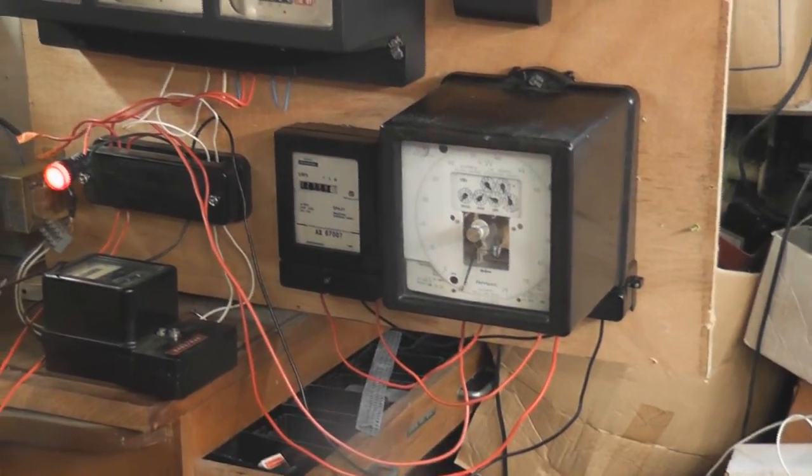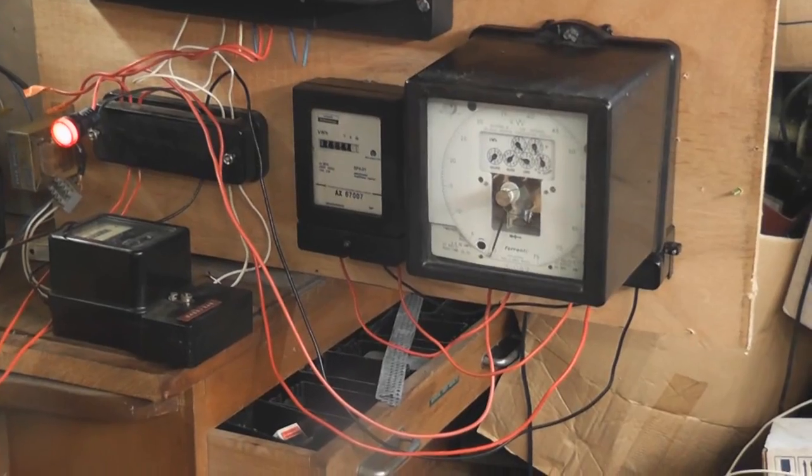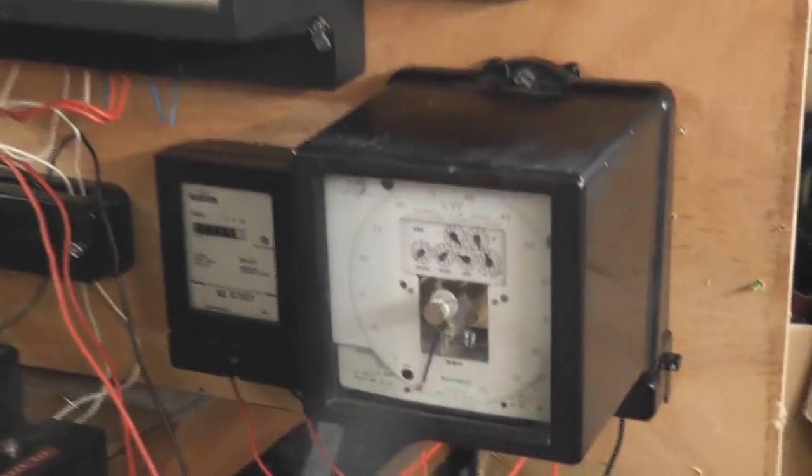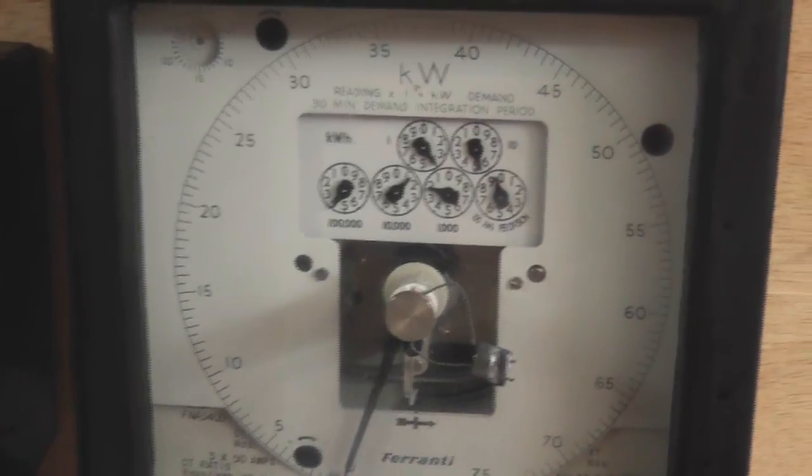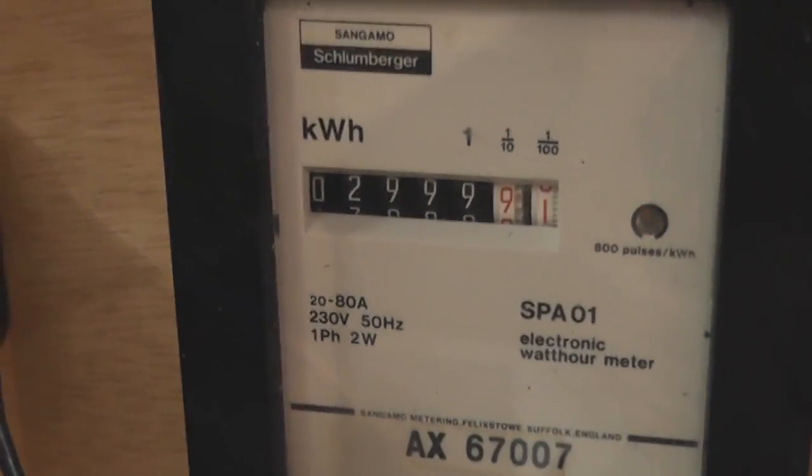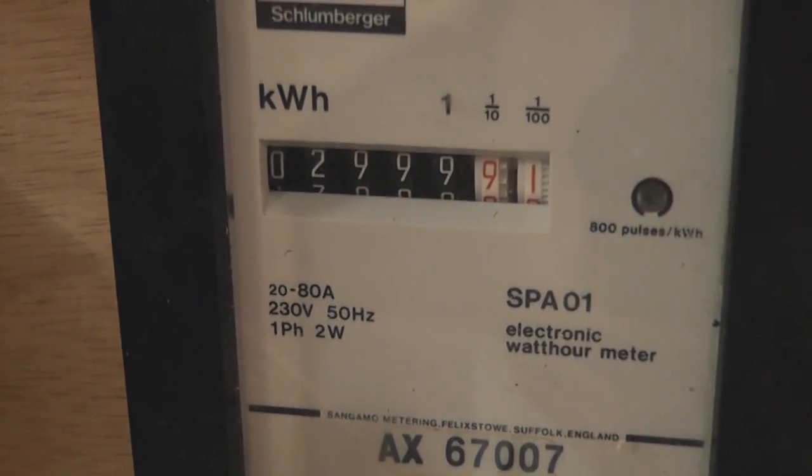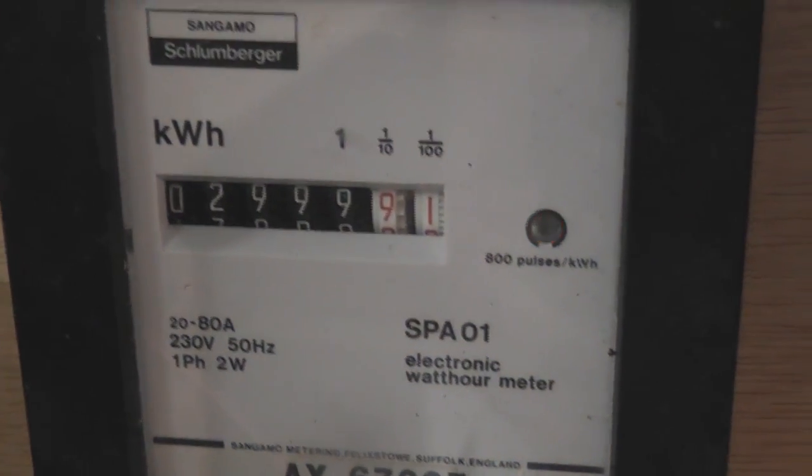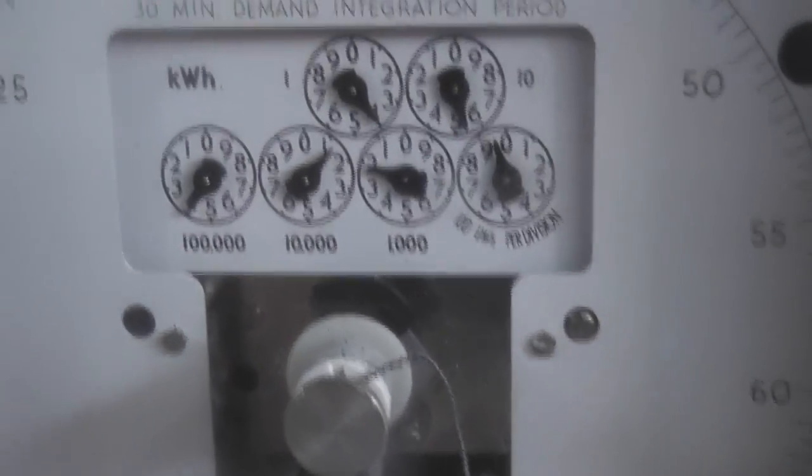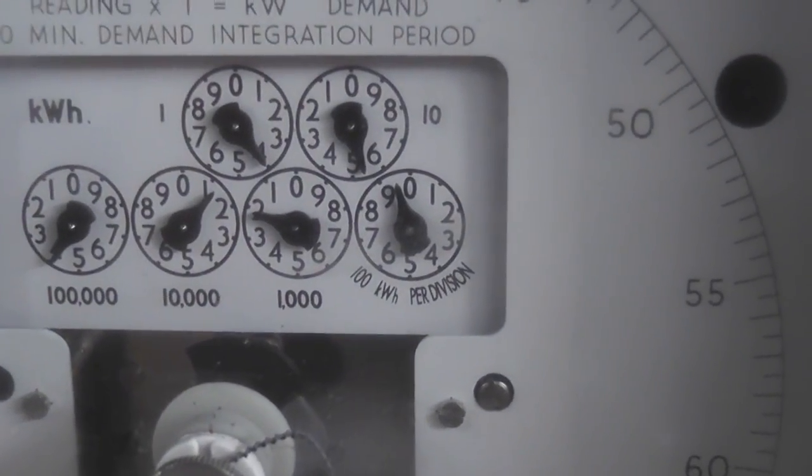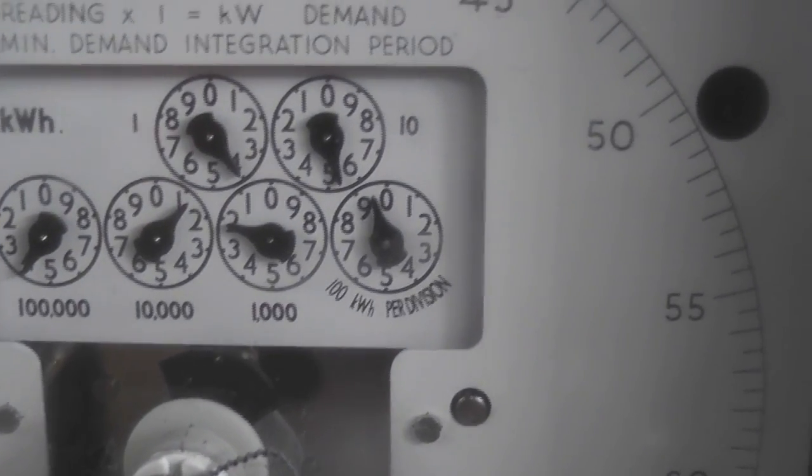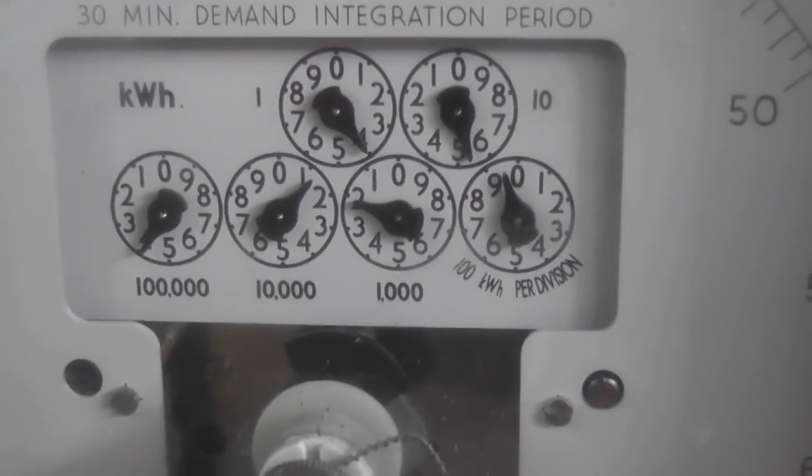So today this video is about a Ferranti maximum demand meter which I acquired about ten days ago and it's quite interesting. So I'm going to do a dial test as I set this up. The start readings initially on this SPA 01 meter, check meter is 2999.91 at the moment and the Ferranti sits on 411954 kilowatt hour.